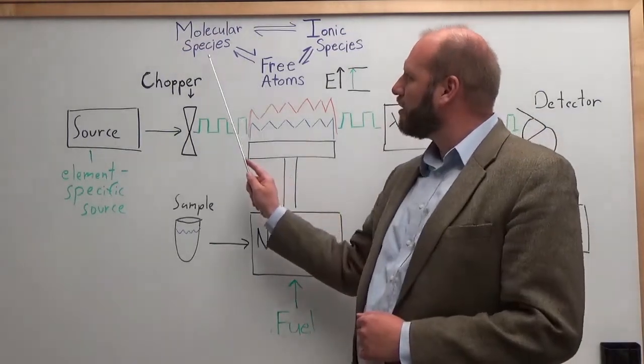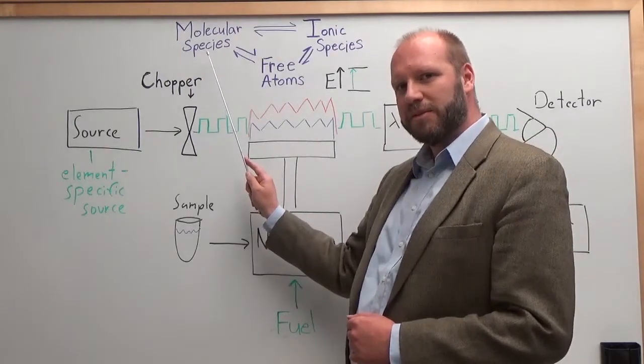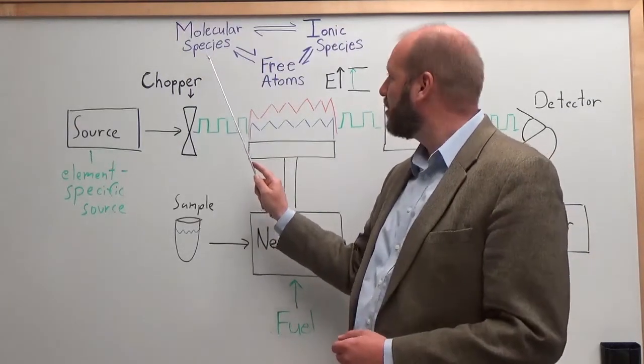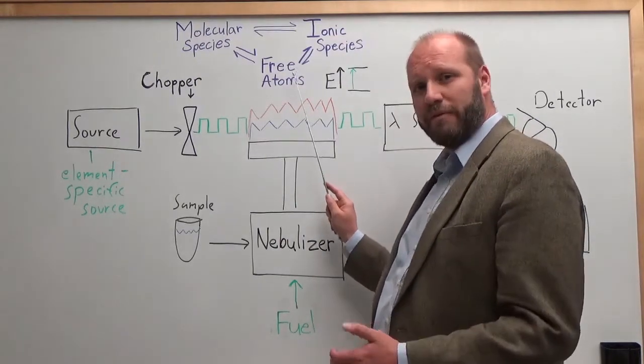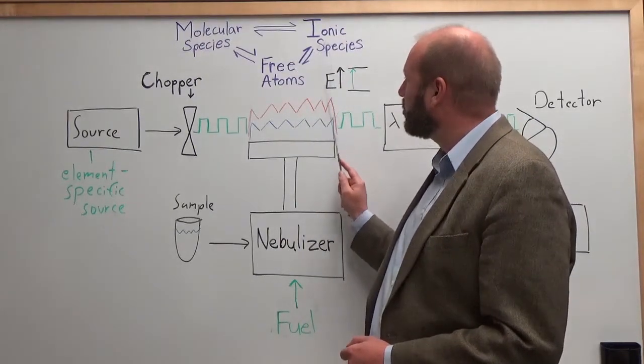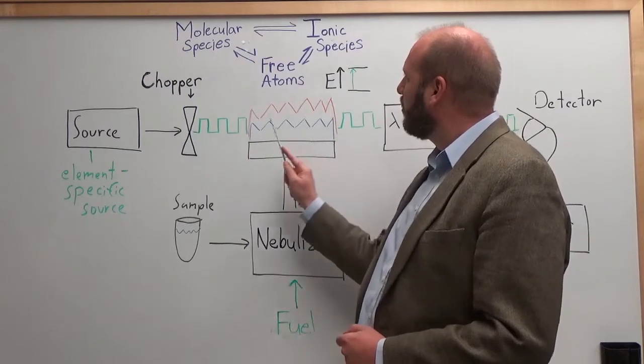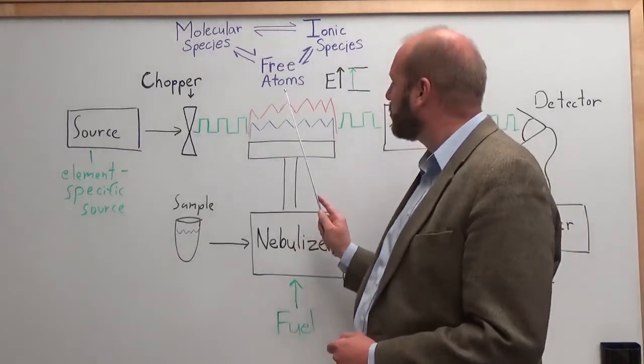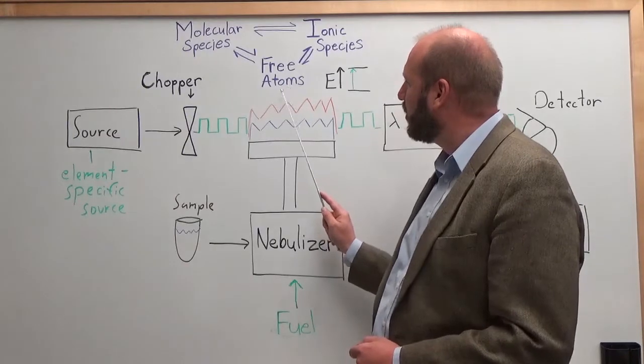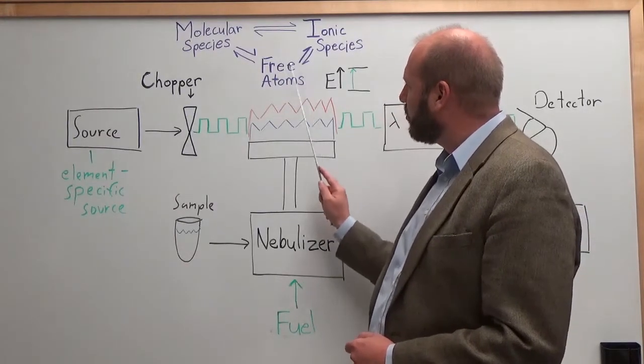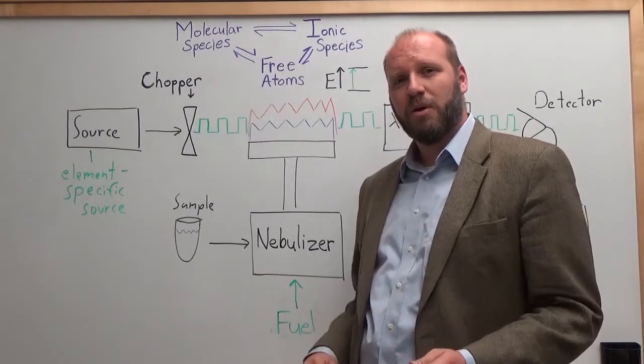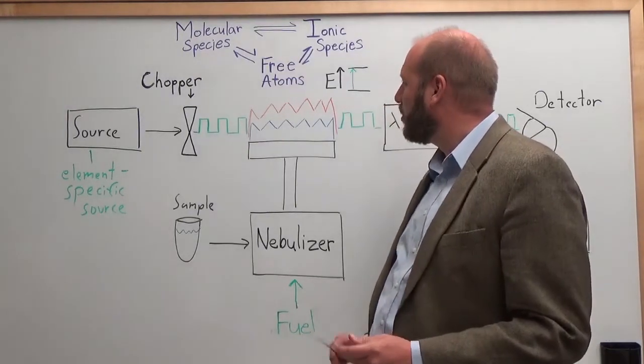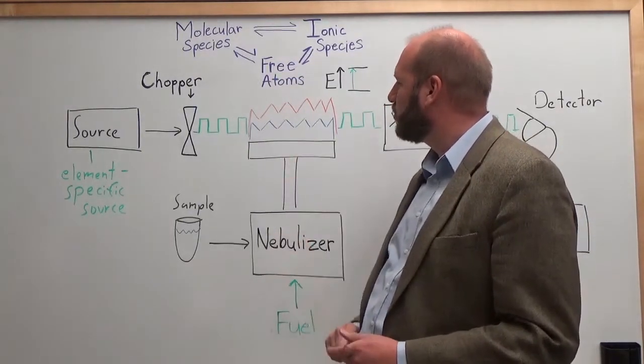However, our atoms can react with other compounds in the flame to give us molecular species. These might absorb differently. Likewise, our atoms can be ionized, removal of electron to form ionic species, which also will have a different absorption profile. Both of these elements are sources of error and you want to minimize or control them in a way that you can. So, we want our elements to be free atoms so that we can measure them. Typically, flame temperature or flame additives is what you can use to control the equilibrium between these compounds.